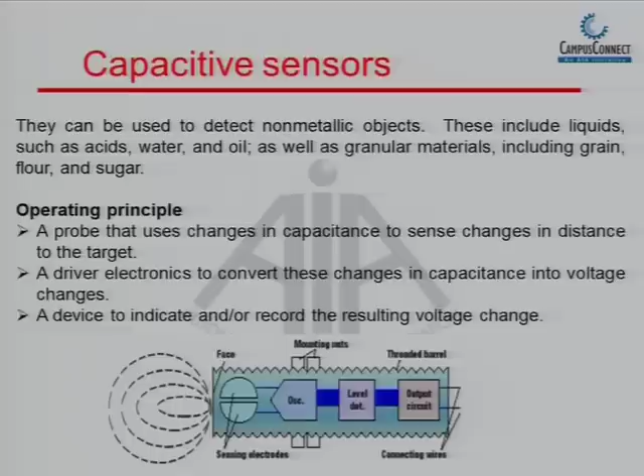Now, if you look at the construction of the sensor, the sensing face of the sensor acts as a plate of a capacitor. The target acts as the second plate. Then again there is an oscillator circuit inside it, a trigger circuit, and an output device. In case of inductive sensors, as I said, as the target approaches, the electromagnetic field gets killed. In this case, the target acts as the second plate. As the target approaches, there is a change in the dielectric field. As a result of that, the oscillator inside the sensor starts to oscillate. This change in state is measured, and we get an output for that. That means its working principle is totally opposite to that of the inductive principle.